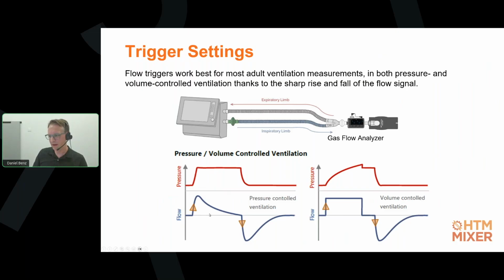And the other good thing about that is they typically don't depend on the setting of the ventilator. So for example, if you have a ventilator where you set a tidal volume of 500 milliliters, and if you set that to 800 milliliters, the flow waveform here is going to change, but the fact that it starts at 0 and rises up at the start of an inspiratory phase and then goes negative at the end of an inspiratory phase when the exhalation phase starts doesn't change. And the same applies for pressure controlled ventilation: whether you have a pressure support of 10, 15 or 20 centimeters of water pressure doesn't change the fact that your flow is first going positive during inspiratory phase and then negative during exhalation phase.